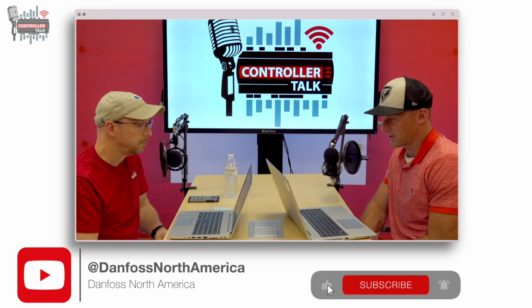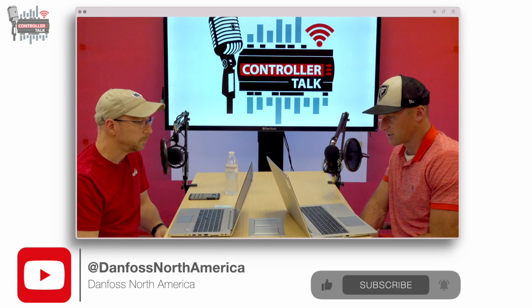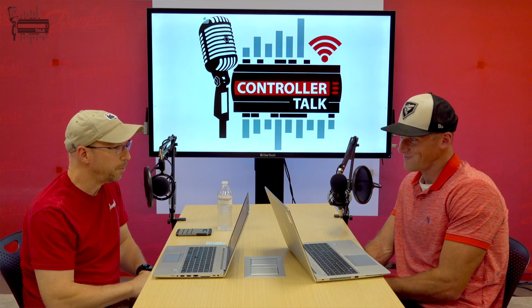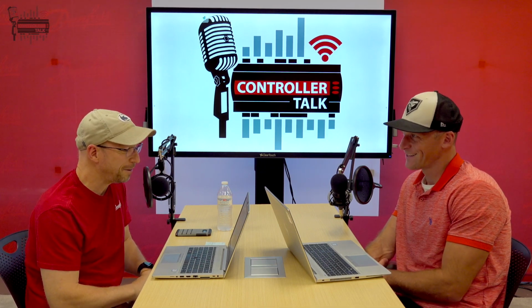On the pressure transducer side, you get into maybe some more limitations here. We can't do more than 5 pressure transducers on each pack controller or extension module. So each individual board, not to say that the overall total can't be more than 5. It can, but when you look at it board by board, you don't want to go over 5 pressure transducers. There's a milliamp threshold on there. 100 or 200 milliamps is what's in my head. I'm not 100% sure, but we'll ask you in one of these podcasts if you know the right number.